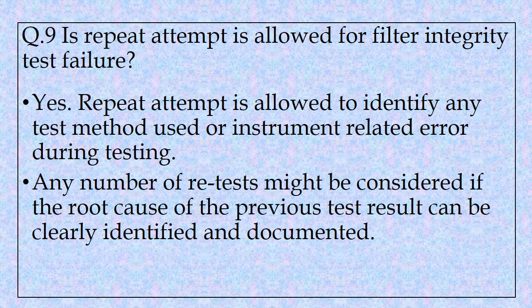Question 9: Is a repeat attempt allowed for filter integrity test failure? Yes, a repeat attempt is allowed to identify any test method or instrument-related error during testing. Any number of repeat tests might be considered if the root cause of the previous test result can be clearly identified and documented.